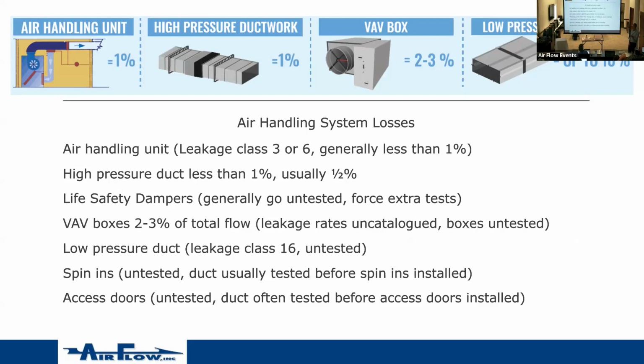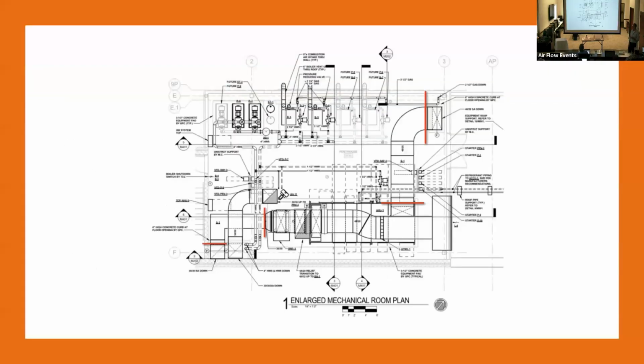Finally, no test on the low pressure ductwork unless you miss on the balance report, and if it gets caught. So we're doing a lot of work up here, and then we're blurping it all out at the end, which kind of sucks. Okay. So where are we gonna put our caps to do pressure testing? Remember, the code says what percentage of ductwork on the inside of the building? 25%. So I've got an air handler, I'm gonna put a cap here so I can test the air handler.